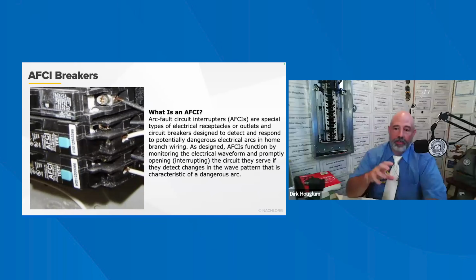Notice the test buttons. They are also the second conductor that connects the breaker to the neutral bars. This is not a double tap. Some earlier Square D AFCI breakers had to be recalled due to manufacturer defects, just FYI.